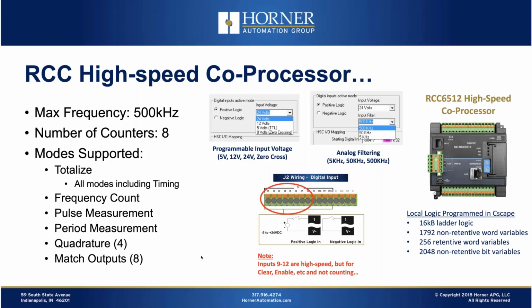And we've got a very good customer that uses this product in quite a big volume. When they first started using the product in their test cells, they were getting spurious readings, and they thought, oh no, we have a problem. A quick phone call and a quick check of the user's manual, and they were able to take advantage of the analog filtering and get rid of their problem very simply.